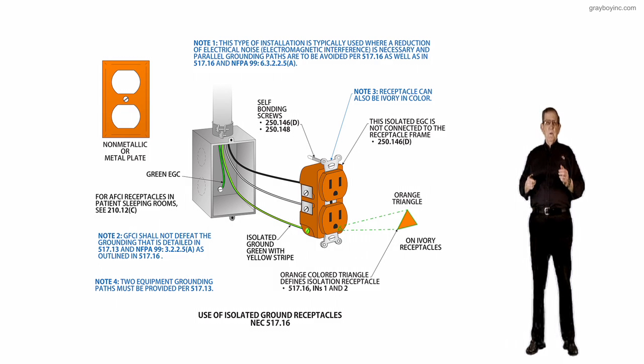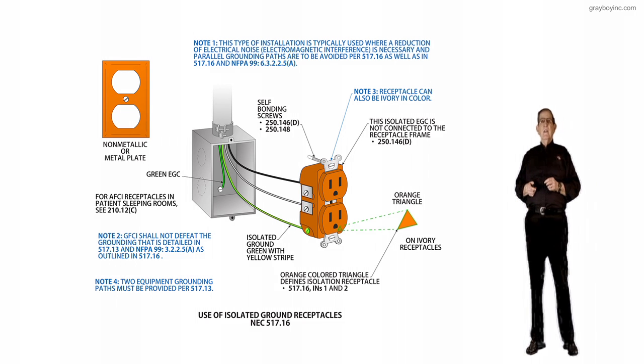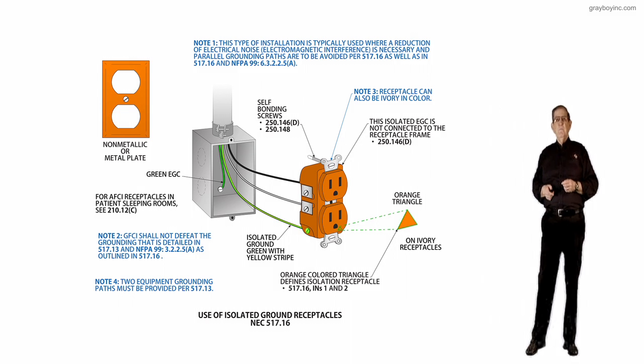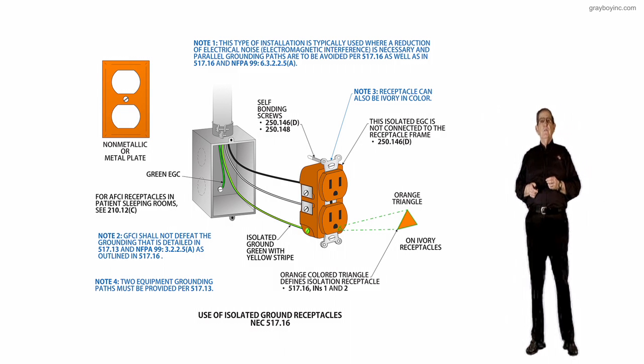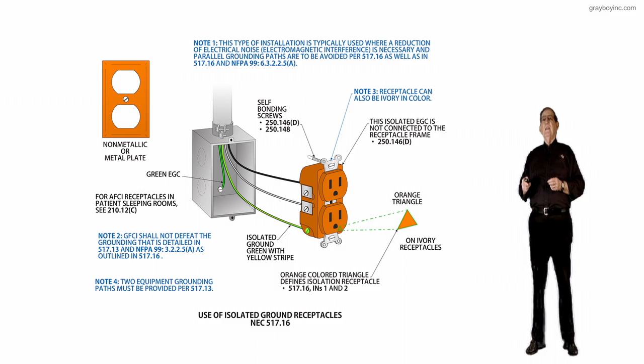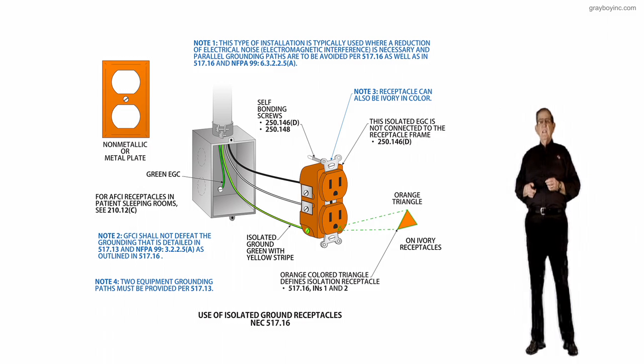If we review note 2, which is right at the very bottom of the device box that housed the receptacle, notice GFCI shall not defeat the grounding that is required in detail in 517.13 as well as NFPA 99 6.3.2.2.5 uppercase A as outlined in 517.16.